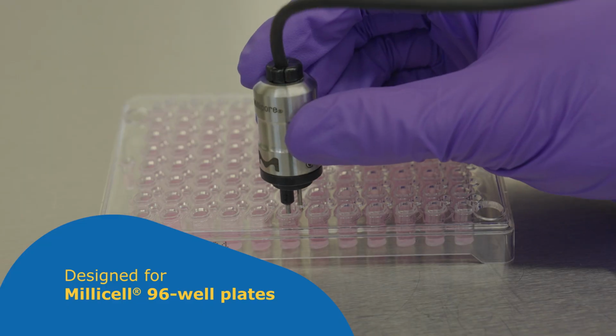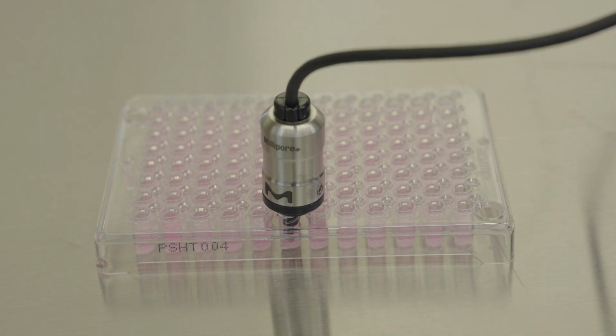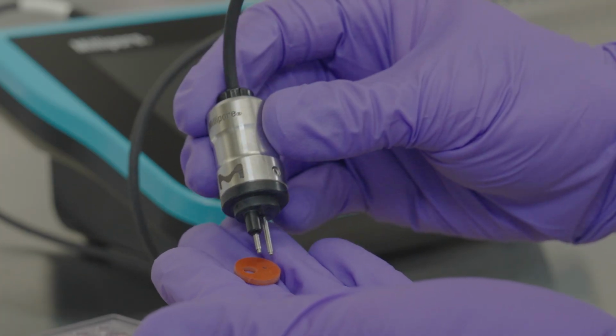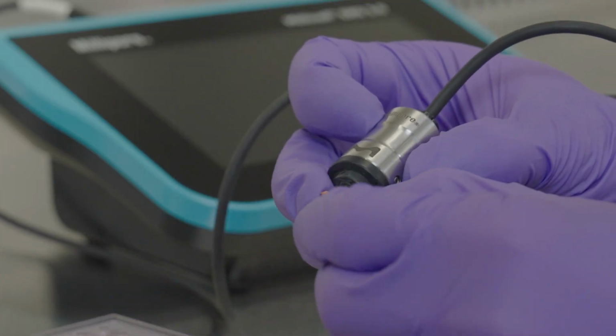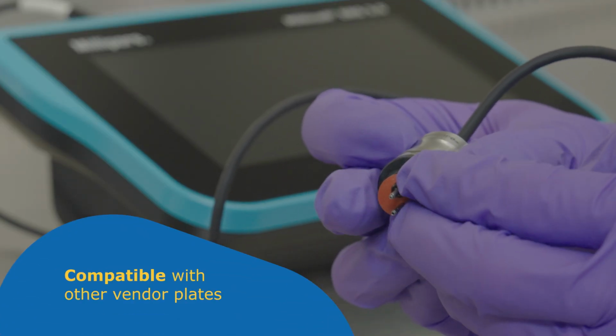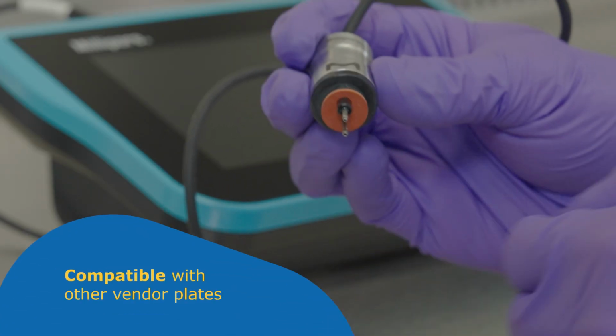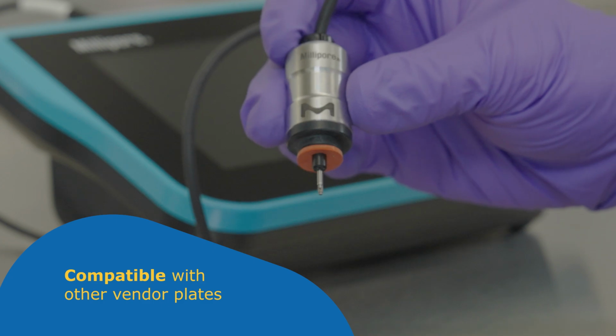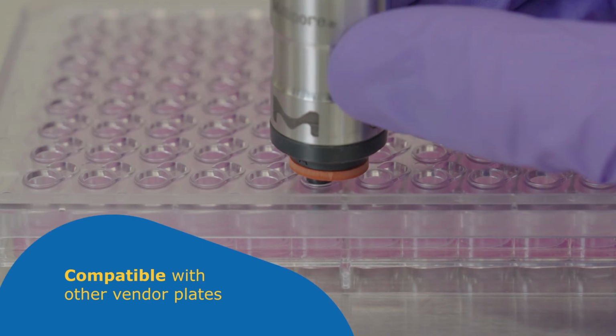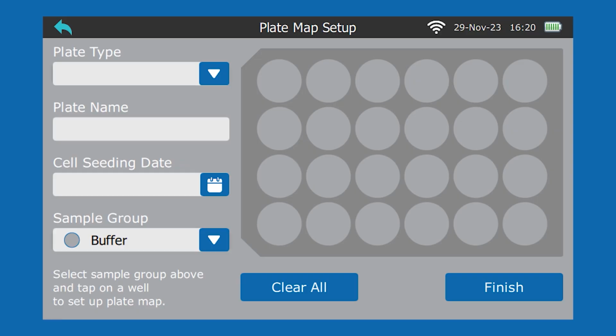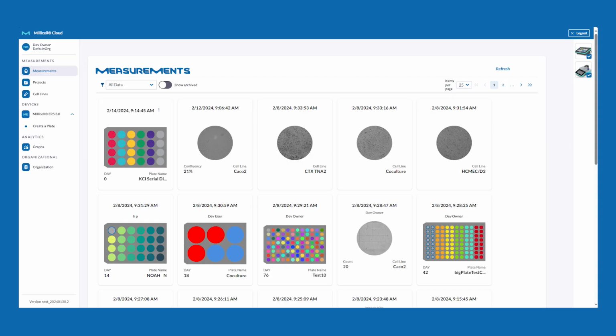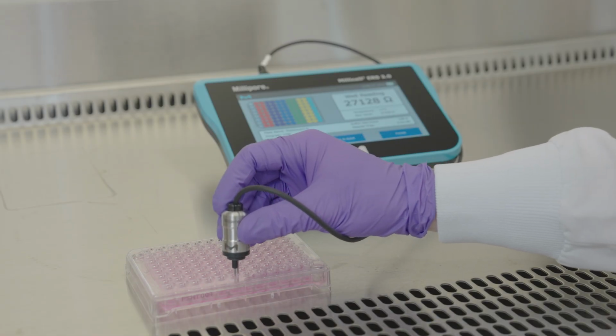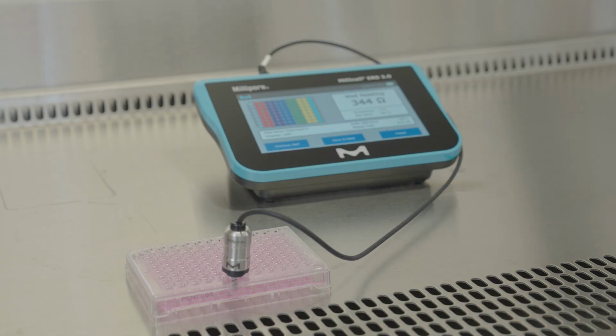This probe was specifically designed to fit our Millicell plates. For non-Millicell cultureware, the 96 well electrode probe requires a silicone spacer for optimal measurement depth. The spacer is required for measurement in transwell and ThinCert cultureware. The Millicell Cloud and plate map features are the same for 6 well, 12 well, 24 well, and 96 well plate formats. Now you are all set to begin using your 96 well electrode probe.